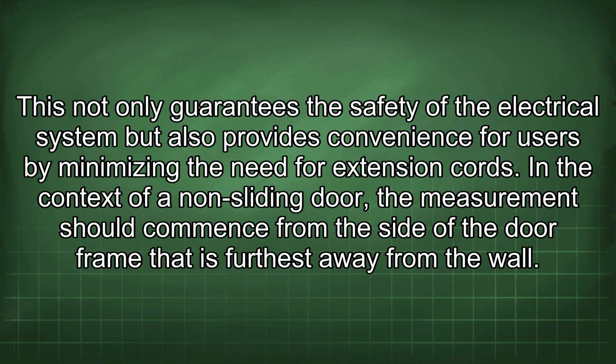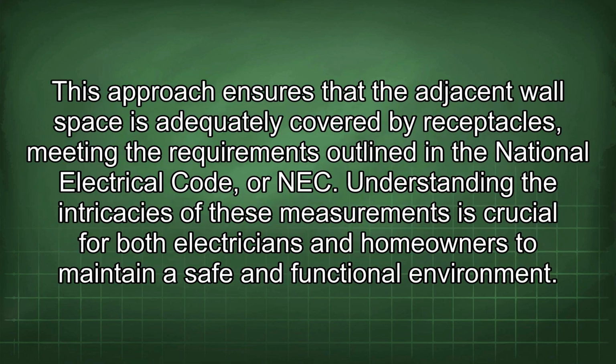for extension cords. In the context of a non-sliding door, the measurement should commence from the side of the door frame that is furthest away from the wall. This approach ensures that the adjacent wall space is adequately covered by receptacles, meeting the requirements outlined in the National Electrical Code, or NEC.